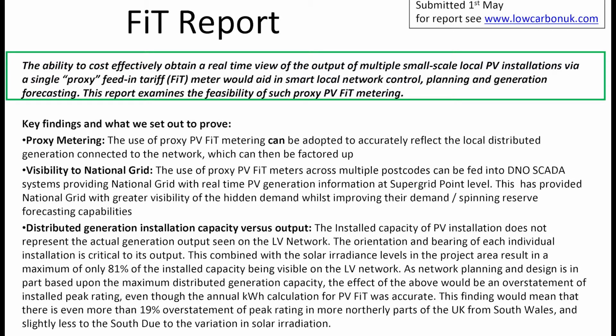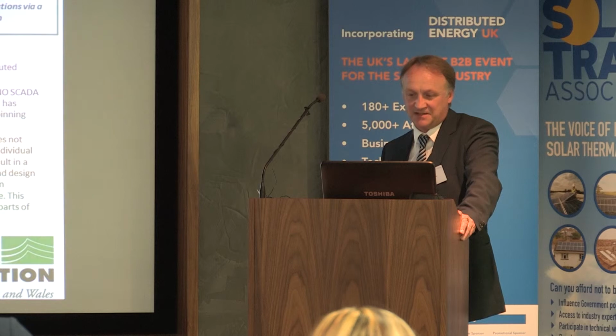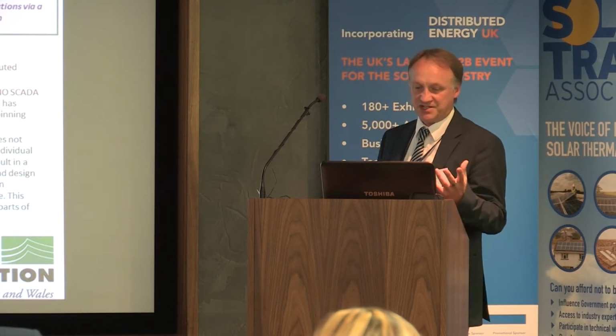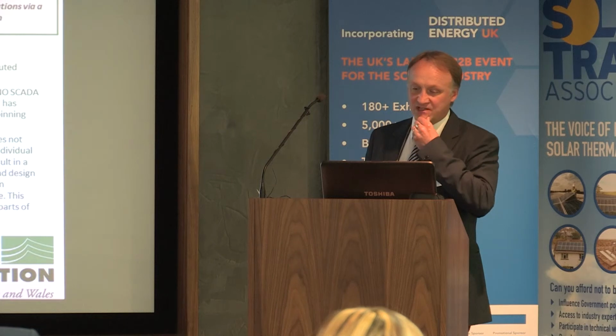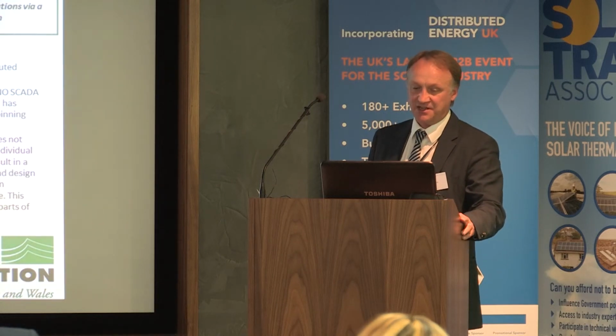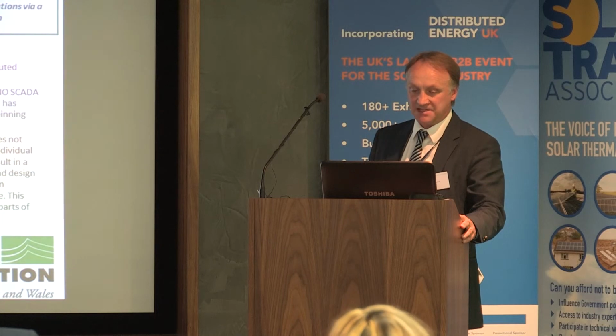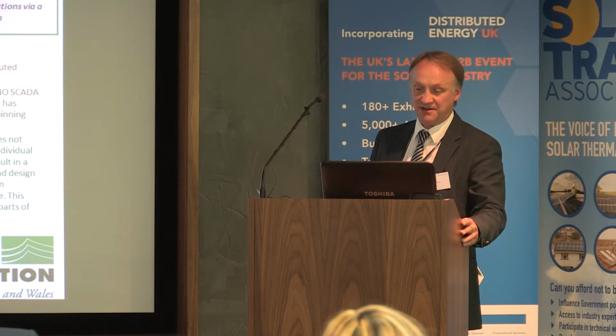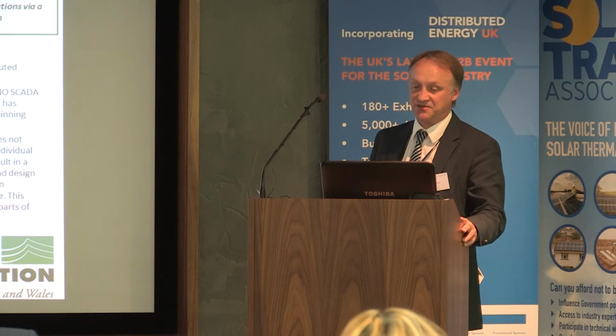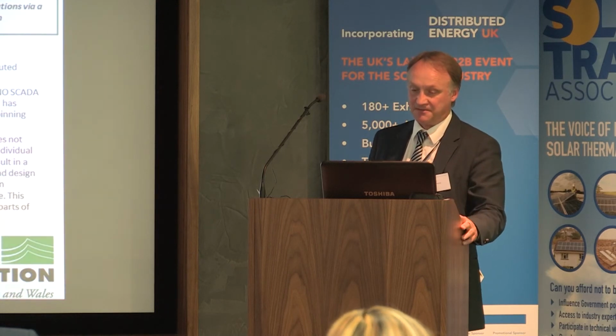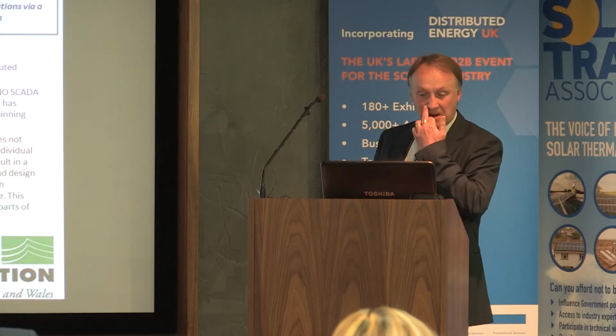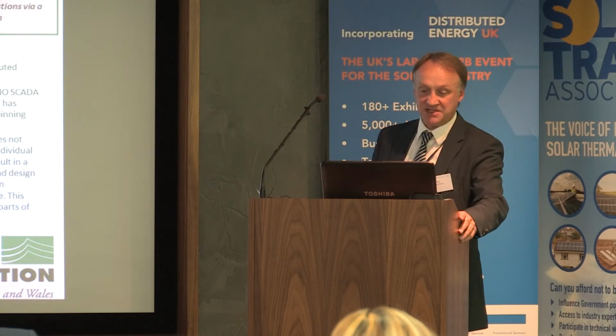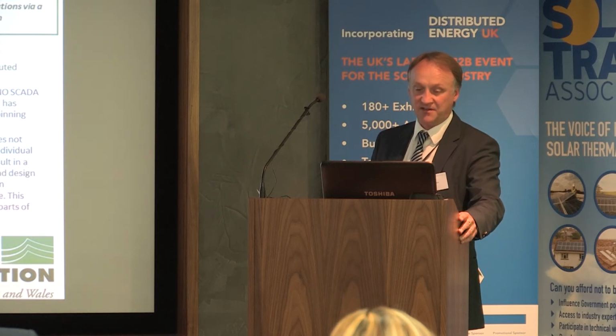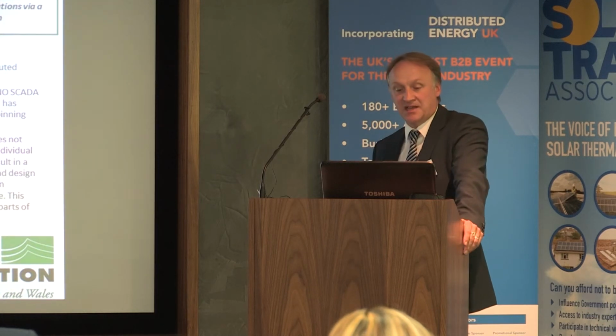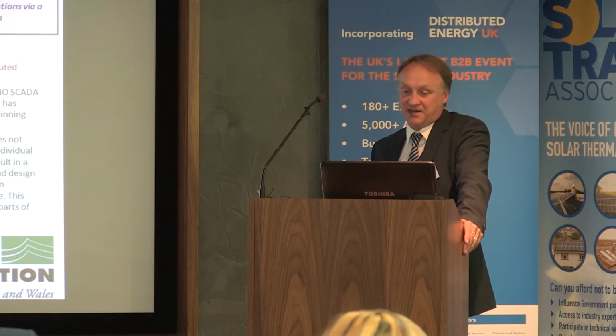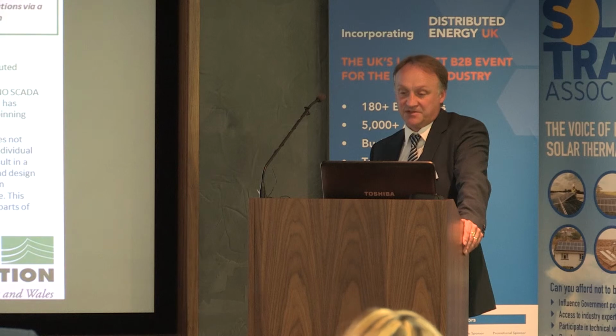Okay, distributed generation capacity versus output. The installed capacity of PV installations does not represent the actual generation output seen on the LV network. The orientation and the bearing of each individual installation is critical to its output. This, combined with solar irradiance levels in the project area, resulted in a maximum of 81% of the installed capacity being visible on the LV network. As network planning is based partly upon the maximum distributed generation, the effect of the above would be an overstatement of the installed peak rating, even though the annual kilowatt-hour calculations of PV feed-in tariff were accurate.